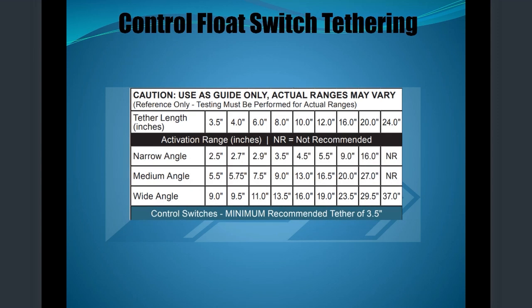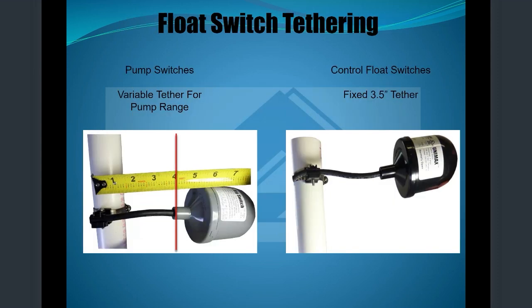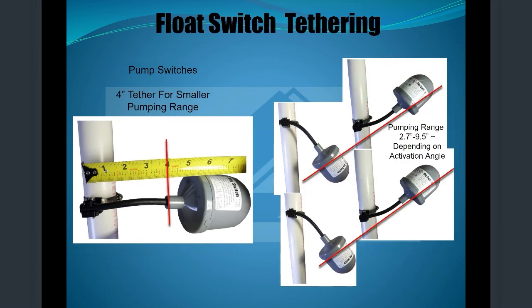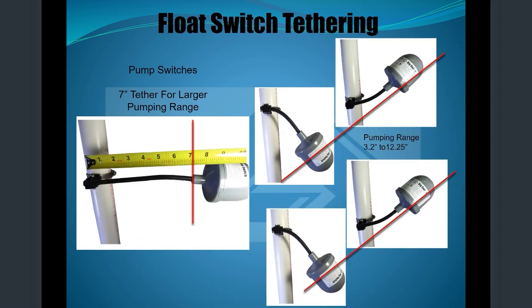And the next slide. So this is the control switch. Typically we recommend the control switches be at 3.5 inches. But if you do want a slightly different activation angle with a narrow, medium, or wide, and a tether length, there's a graph for that to show you how much tethering you'll get. So this talks about variable length for your pump range, and then fixed for control switches typically. It shows the activation angle and how many inches of pumping range you would get. Okay, next up. That's a 7-inch tether, which is 3.2 to 12.25 inches.